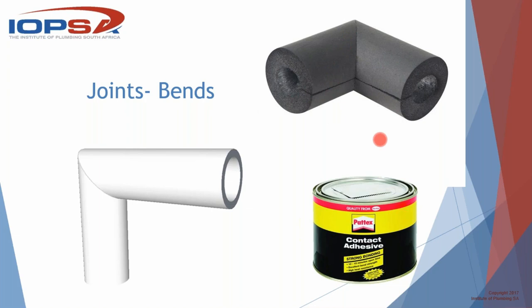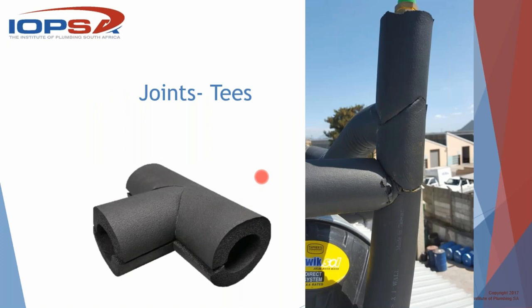So joints can be made with mitering. They are for larger diameter pipes. You would probably make a 90 degree bend in sections of three or four 22.5 degree sections for larger radius bends and larger diameter pipes. But as I say, each to his own, and each job will have its own requirements.